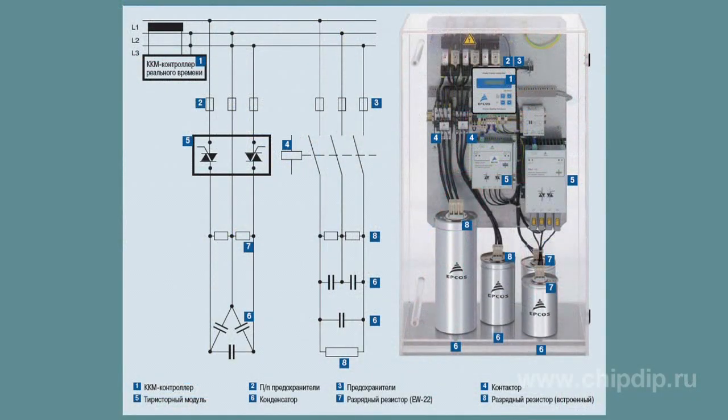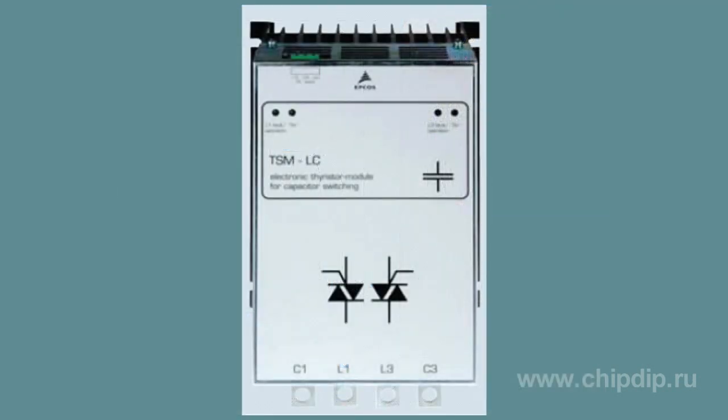This problem can be solved by using dynamic power factor correction systems. TSM-LC and TSM-HV modules are the key components — electronic switches in dynamic power factor correction. TSM modules are electronically controlled thyristor switches for capacitive loads up to 200 kVAR. These devices are able to switch corrector capacitors in a couple of milliseconds without any limitations during the service life of capacitors.